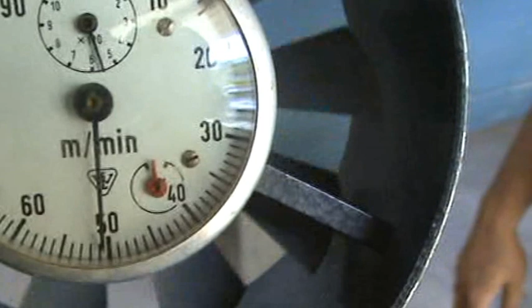We have already taken the readings, both static pressure reading and also the anemometer reading, without the diffuser. Now we are going to take the readings with the diffuser attached at the outlet. So this is the diffuser which is attached at the outlet of the fan, and the area ratio of this cross section is 4:1. So now take the reading with both static pressure reading, and also we will do the traversing at the inlet of the duct to find out the efficiency.